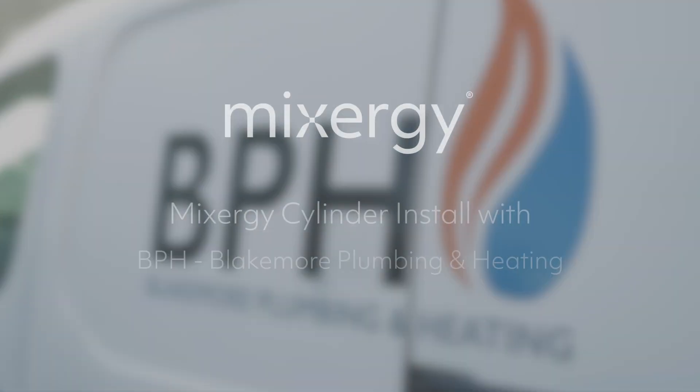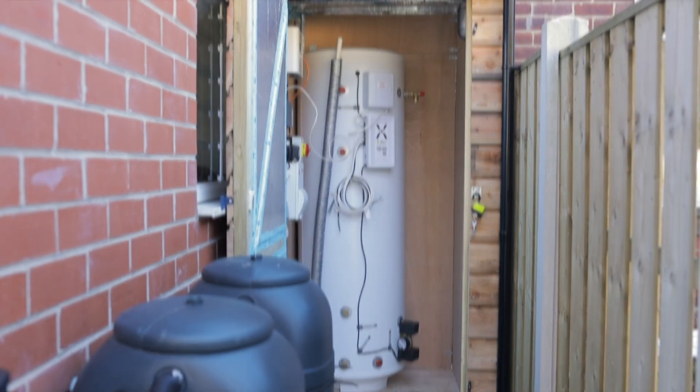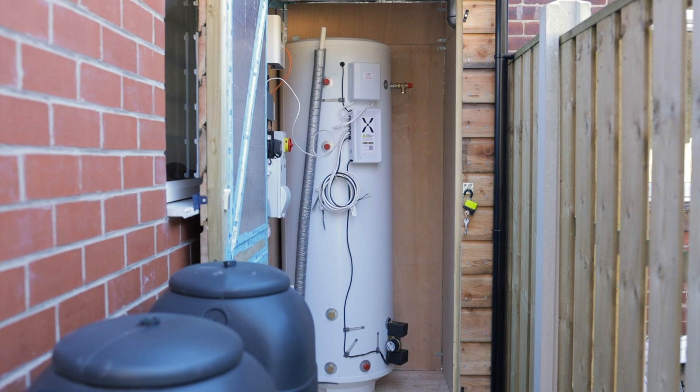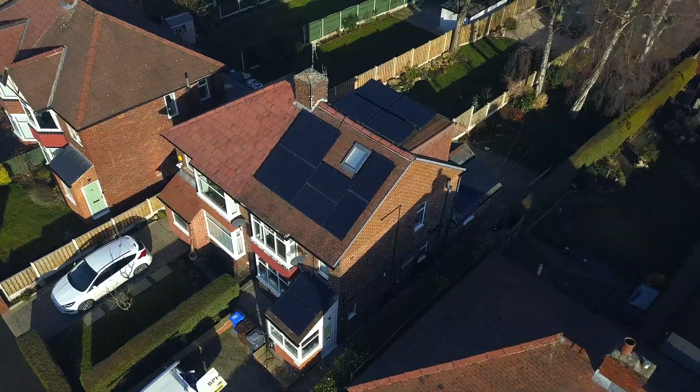Damon Blakemore from BPH — today we've installed a Mixergy cylinder. It's a Mixergy 250 litre direct cylinder, so it doesn't have a coil. A plate can be attached to it so we can plate-load it when we go with a heat pump, but solely for now we're just charging it off the immersion heater, which is a PV one as well, so we can divert from his solar and battery storage.